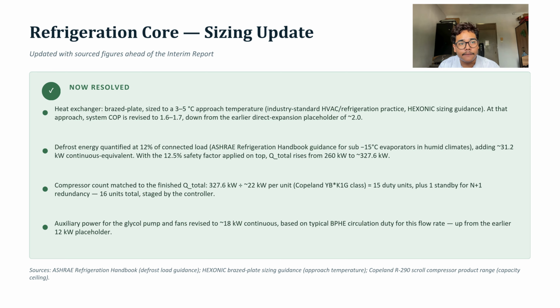Second is the defrost energy, the extra energy used when the coil is practically made of built-up ice. Using the ASHRAE guideline for this type of room in a humid climate, that is about 12% on top of the base cooling load. Once we add that in with our safety margin, the total cooling requirement goes from 260 kilowatts up to 327.6 kilowatts. Take the compressor count, that's where the 16 units come from. The 327.6 divided by 22 kilowatts gives us the 15 units, plus the one that we have as our spare.